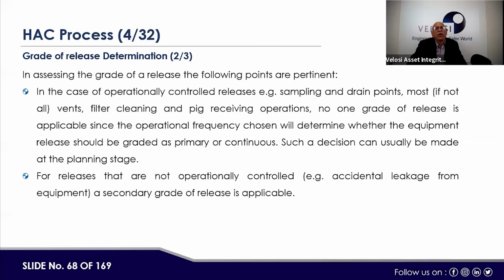Similarly, we have to see how much fluid would be coming out. In the case of operational control release, for example, sampling and drain points, most, if not all, vents, filter cleaning, and pig receiving operation, no one grade of release is applicable, since the operational frequency chosen will determine whether the equipment release should be graded as primary or continuous. Such a decision can usually be made at the planning stage. For releases that are not operationally controlled, for example accidental leakage from the equipment, secondary grade of release is applicable in that scenario. All accidental releases are called secondary.